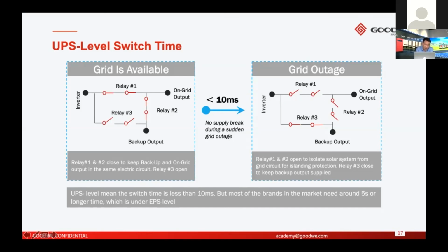That's why, as I mentioned on the previous page, if the grid is normal, the off-grid loads and on-grid loads have no priorities, because the backup output and the on-grid output are in the same parallel system. If the grid fails and it switches to off-grid mode, these relays will open for anti-islanding protection, and this one will also open because there's no power from the grid side. But these relays will close to make sure the backup side still has power supply from the inverter. This is the general working logic of the UPS switch time.